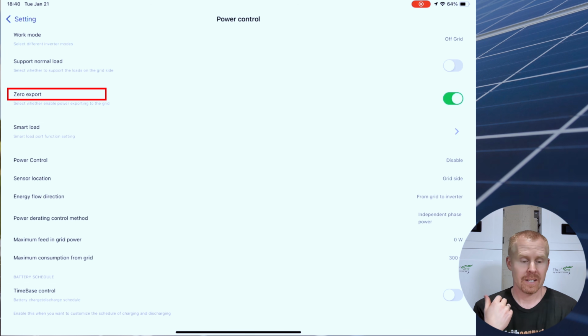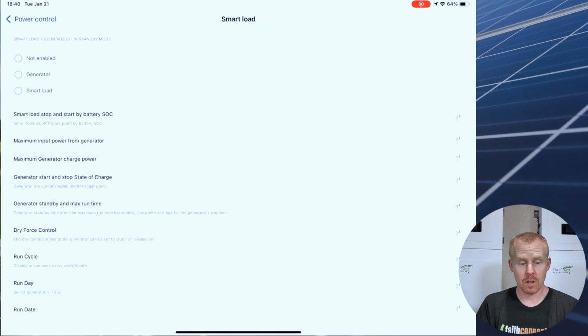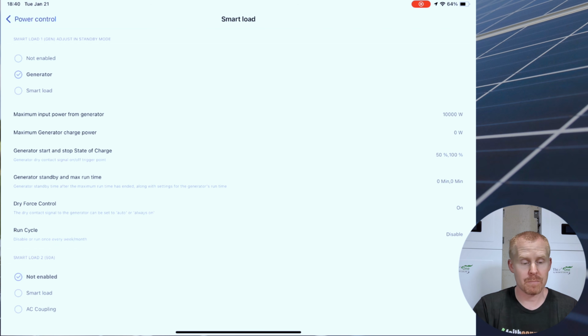Zero export is pretty much exactly like what it sounds. Are you going to allow your system to export power to the grid? Yes or no? If this is turned on, the inverter will prevent power from being pushed past your CT connections. Smart loads. This inverter has three different smart loads: a 30 amp, a 50 amp, and a 60 amp. The 60 amp smart load is going to either be for a smart load or for generator. The 50 amp is going to be for a smart load or AC coupling. And then the 30 amp is only a smart load.